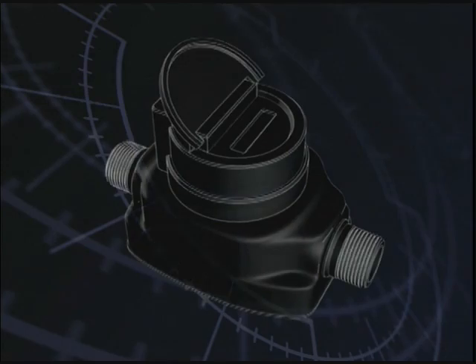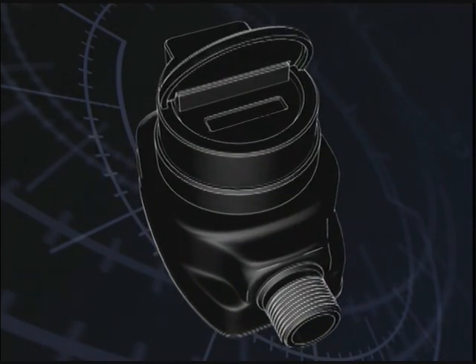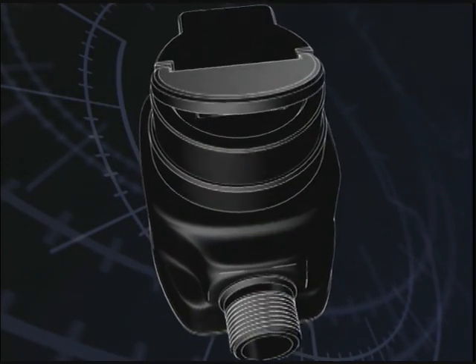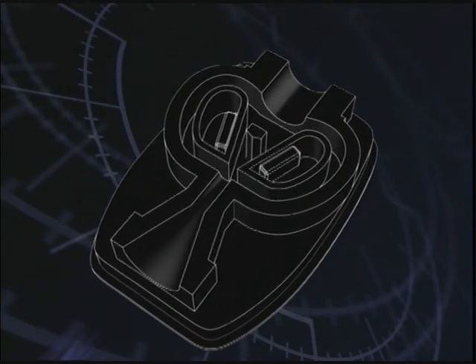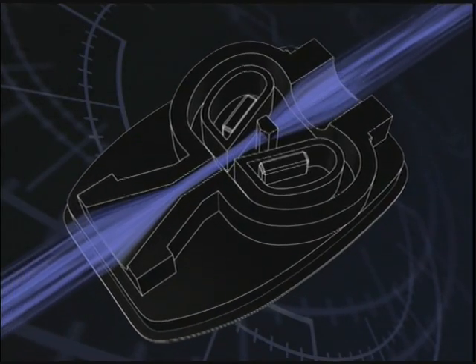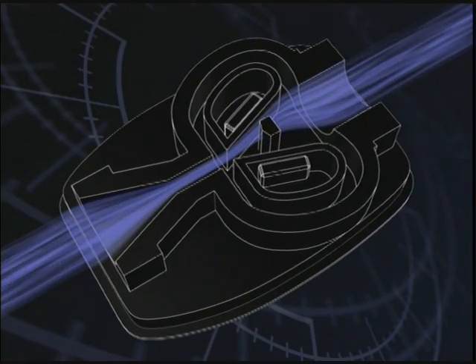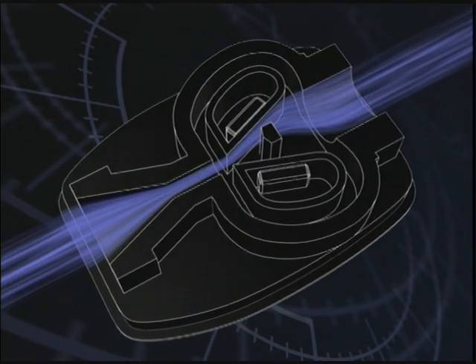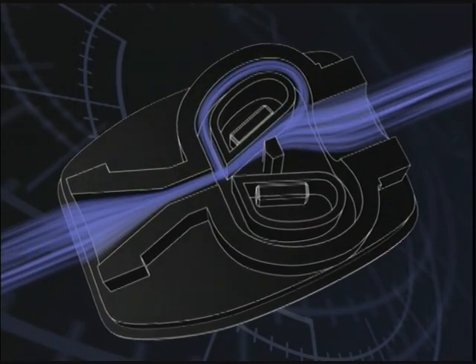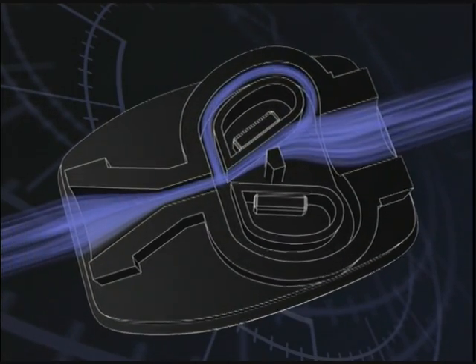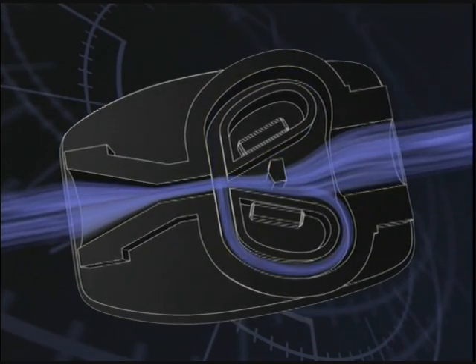Another type of small residential meter, recently introduced, is the fluidic oscillator meter. In these meters, water enters through a nozzle and forms a jet. This jet of water is drawn to one of the two diffuser walls as it passes through the flow chamber. A small portion of water is passed through the feedback channel and causes the incoming jet to flip to the other side of the chamber, where the process is repeated.